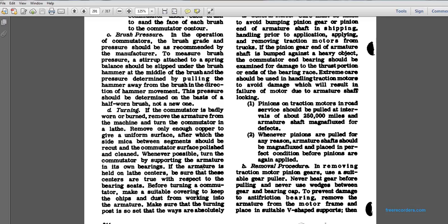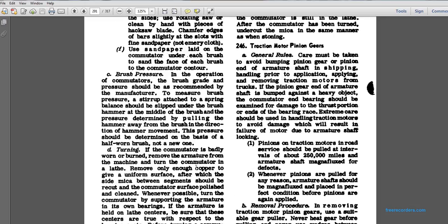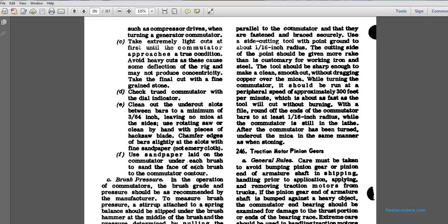If the armature is held on the lathe centers, make sure that these centers are true with respect to the bearing seats. Before turning the commutator, make a suitable covering to keep the chips and dust from working into the armature. Make sure that the turning post is set, that the ways are absolutely parallel to the commutator, and that they are fastened and braced securely.